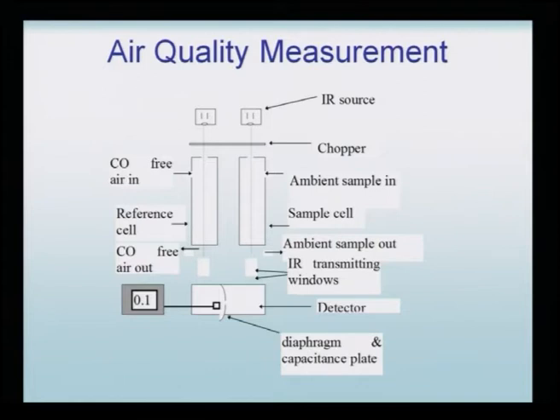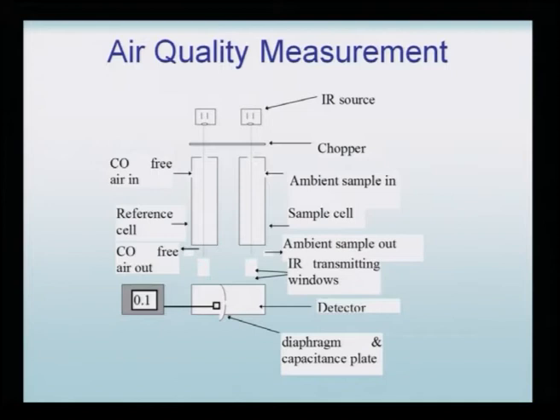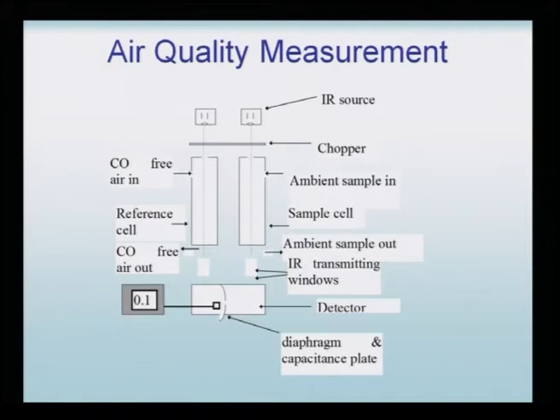This is how the instrument looks. There is an IR source and then two beams are made to pass. There is a chopper which puts only one type of IR radiation into the device. Carbon monoxide-free air is passed through one beam and through the other the ambient sample is passed. They go parallel, there is a reference cell, and it is passed on to the detector with a diaphragm. Finally, the analytical spectrum is derived from this measurement device.